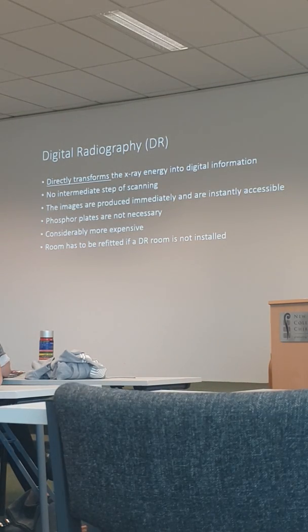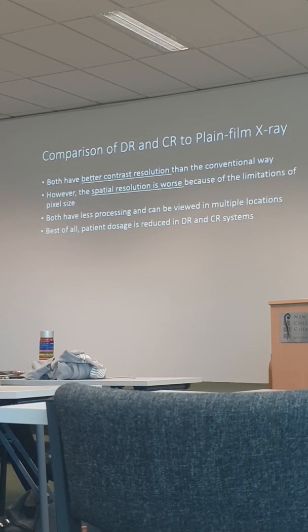Digital radiography, much better. No in-between step now. It'll directly transform the X-ray energy into digital information and send it straight to the computer. So you don't have to do that intermediate step of scanning. You don't need phosphor plates, but it is a lot more expensive than the other one. But once it's fitted, there's much less ongoing cost. You don't have film, darkroom, all that sort of thing. And you have to refit a lot of it if you don't already have a digital suite installed.